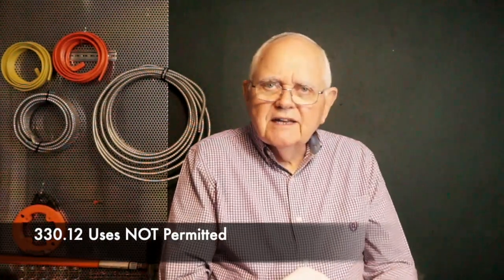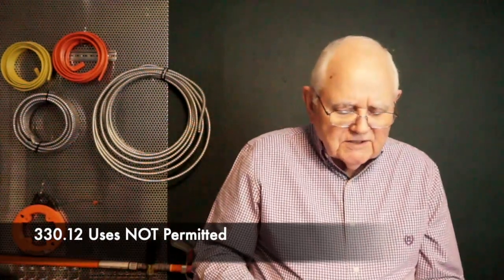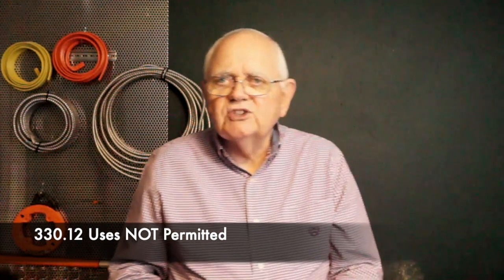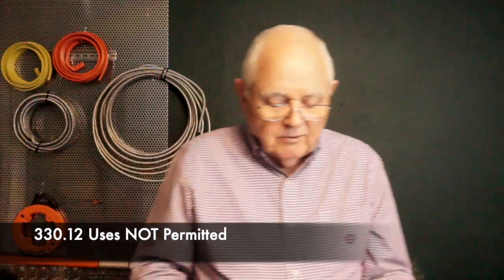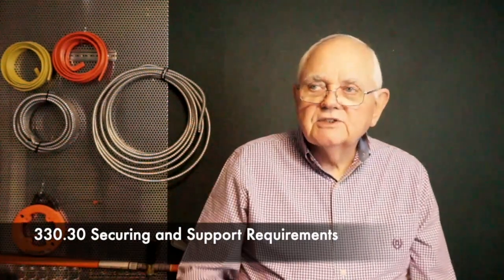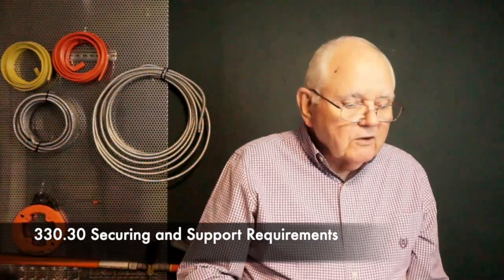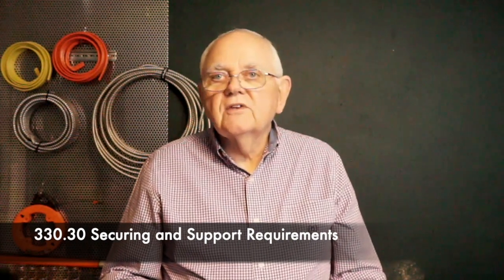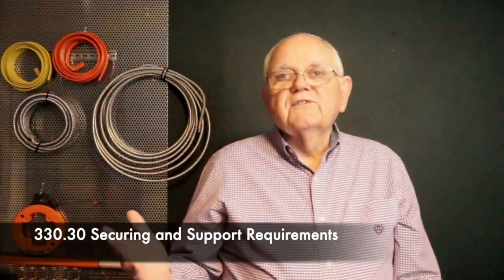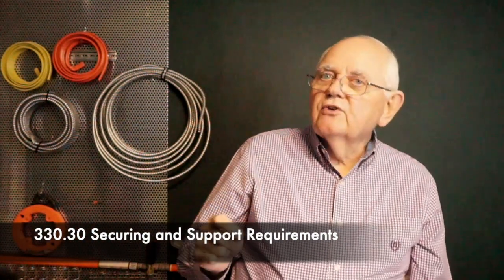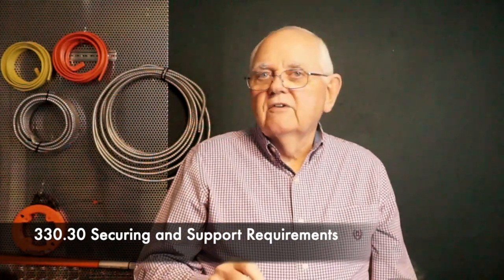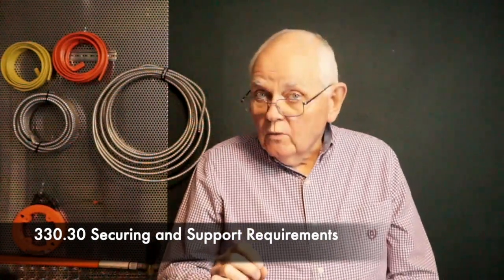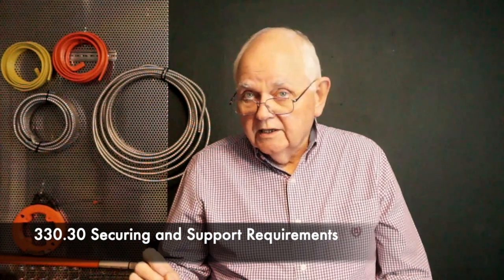Uses not permitted should make some sense to me. At least the first one, where we're subject to physical damage. I wouldn't want to use MC cable where it's going to be damaged. Now, .30 is my support requirements. General support requirements, every 6 feet, and it has to be secured within 12 inches of a box. Two different words, securing and supporting.